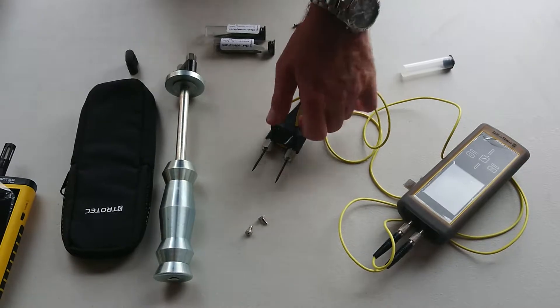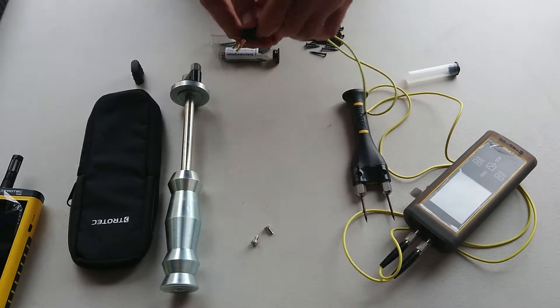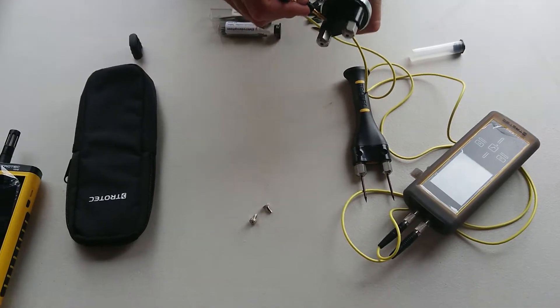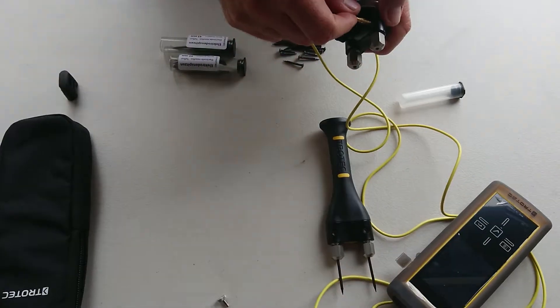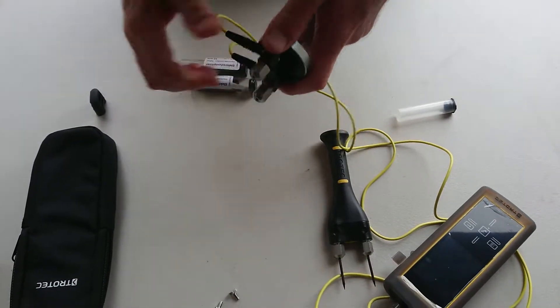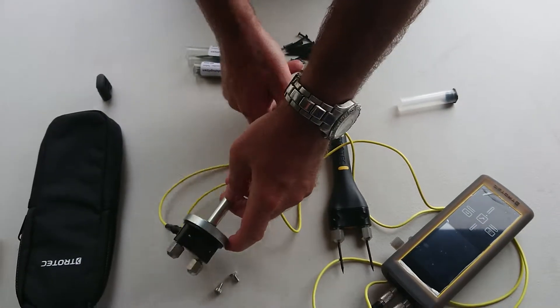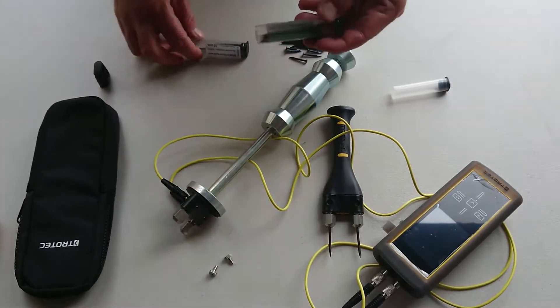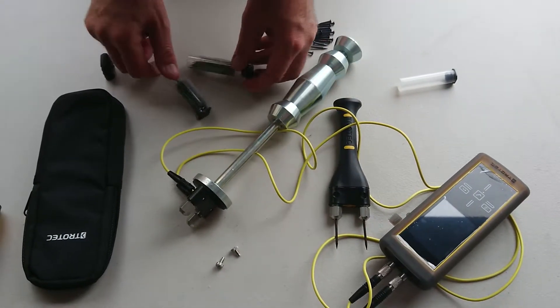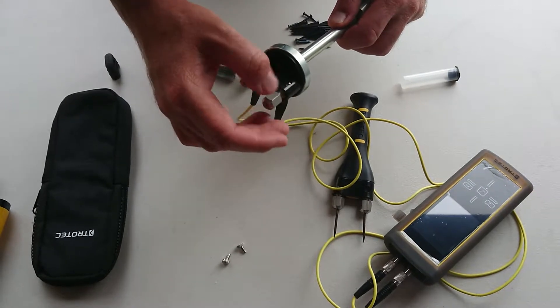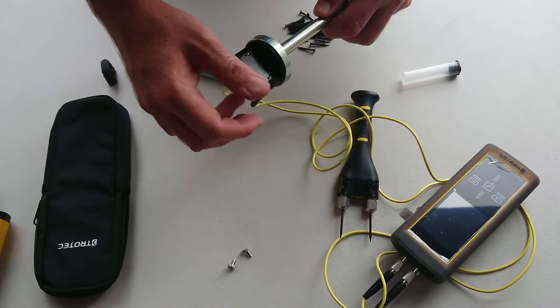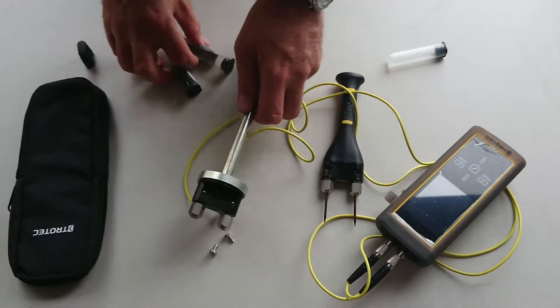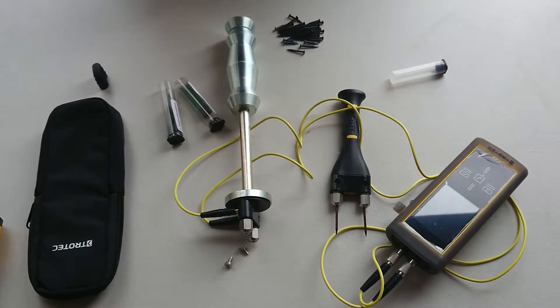Then you have an option also to set up your hammer probe. So once your hammer probe is set up, just like so, we have different size pins. We have 60mm and 45mm that can go in here into our hammer probe, just like so. So that's how to set up your hammer probe with your insulated pins and your pin probe with your non-insulated pins.